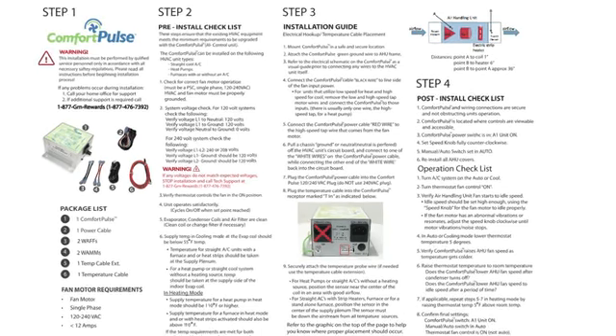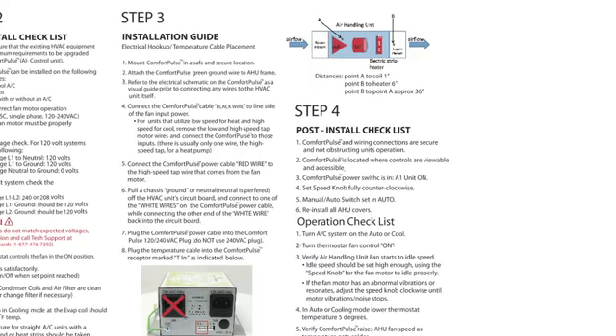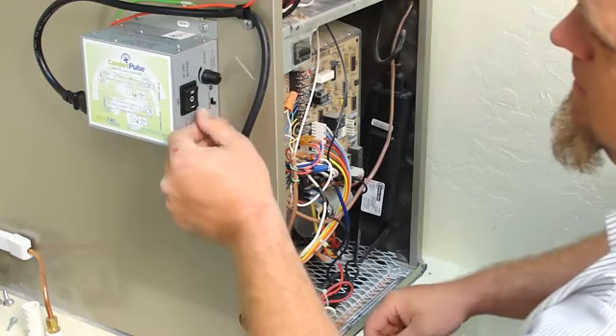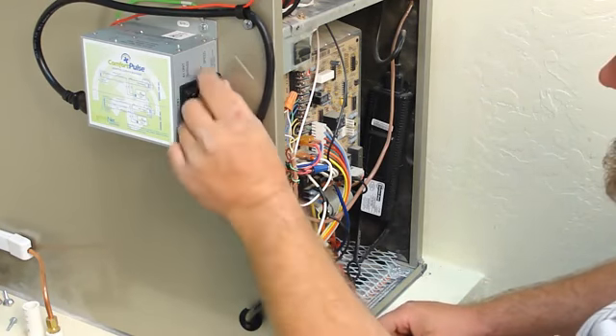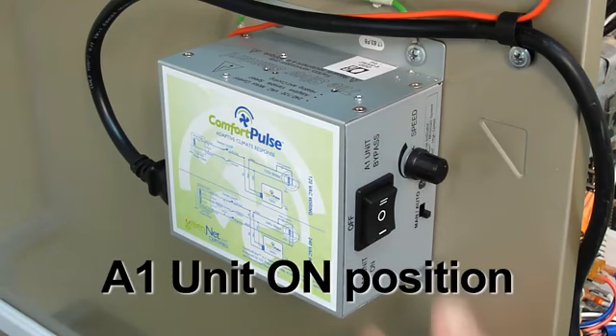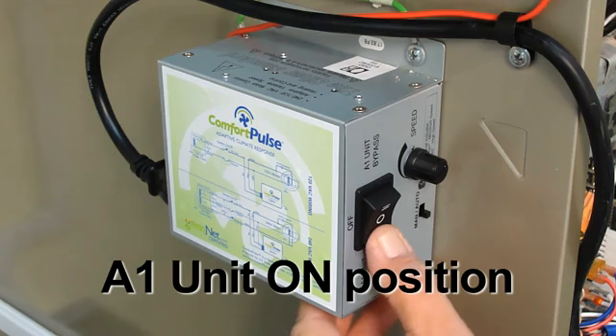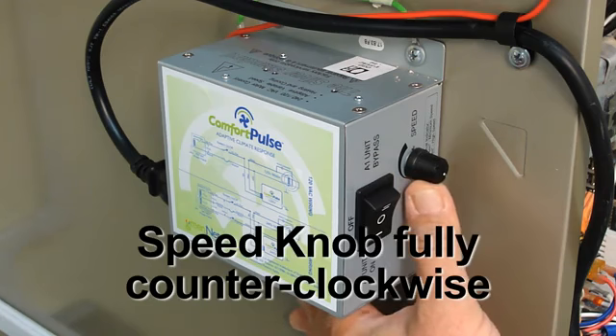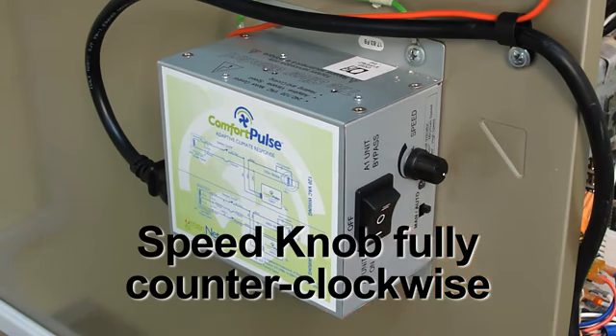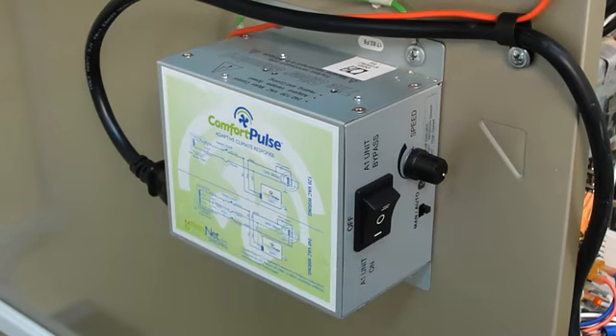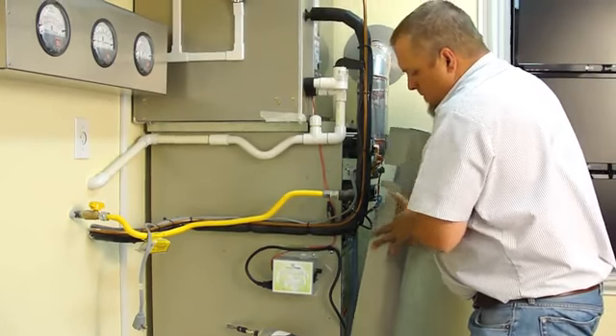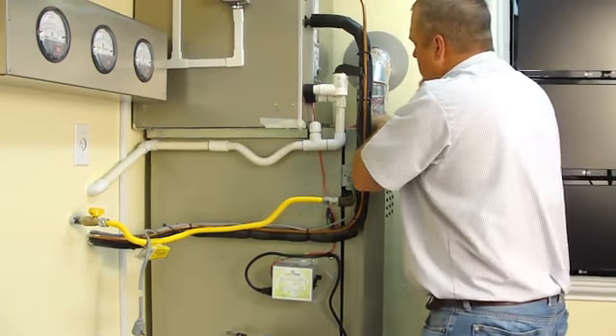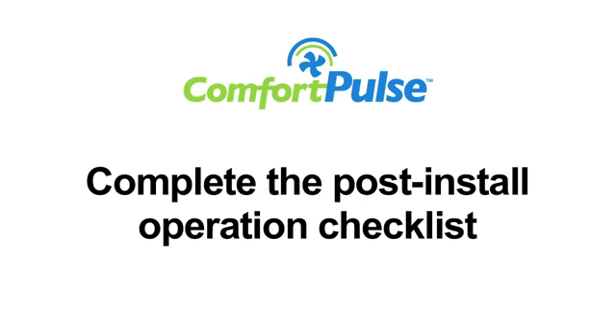Now that you have installed the Comfort Pulse, we need to perform some post-install checks to confirm that the Comfort Pulse and wiring connections are secure and not obstructing the unit's operation, that the Comfort Pulse is located where its controls are viewable and accessible, that the Comfort Pulse power switch is in the A1 unit on position. Make sure to set speed knob fully counterclockwise with the manual auto switch set to auto. Finally, reinstall all of the air handler unit covers. Now, to complete the installation, we will complete the post-install operation checklist.